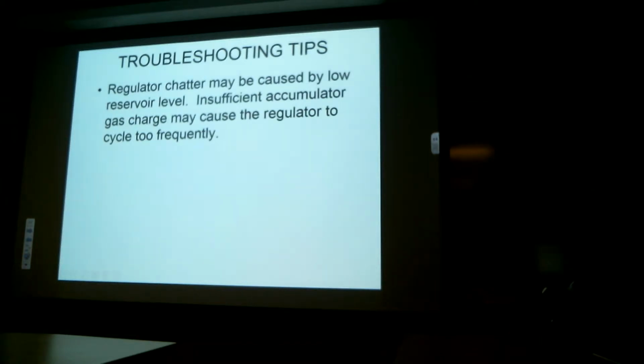This is a good lesson maybe to remember. Sometimes a symptom will develop someplace in the circuit, but the problem is really another component. So in this case, the regulator chatter, what I suspect is the regulator is cycling too frequently, and what might be causing that is the inability of the accumulator to hold the unloading valve in the kicked out position. It's transitioning back to kick in too suddenly, so that'll cause chatter. Actually, a better way to define what's happening is the cycle time is too short. You're going from kick out back to kick in in too short a period.